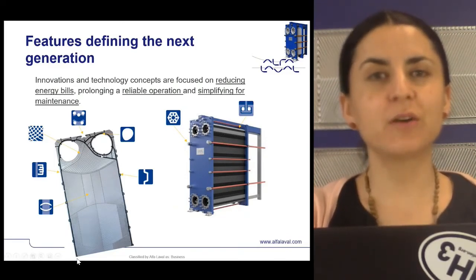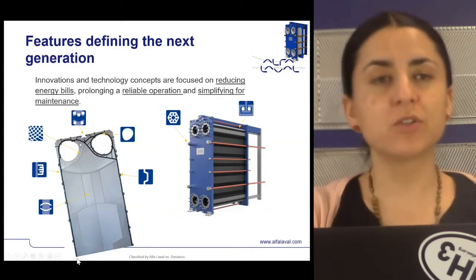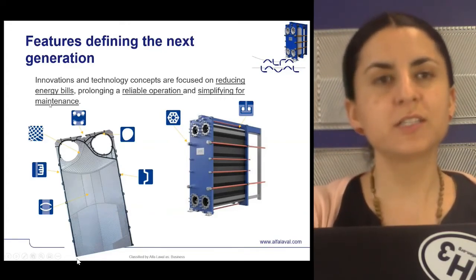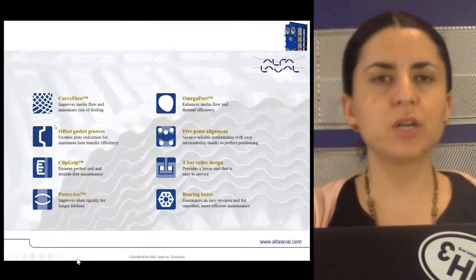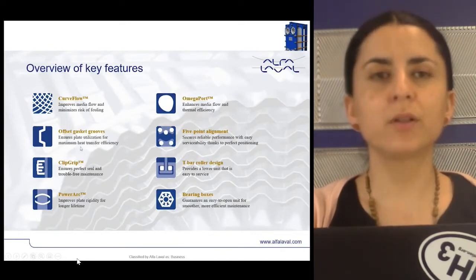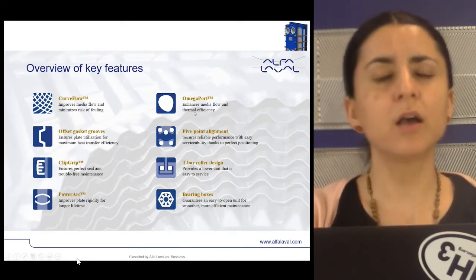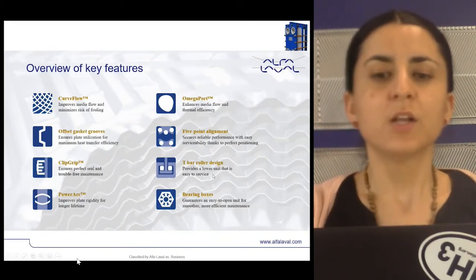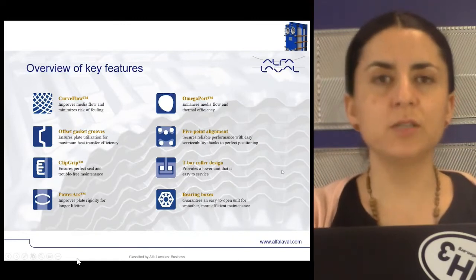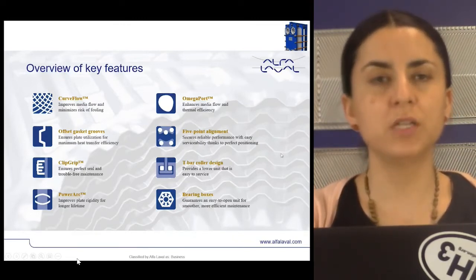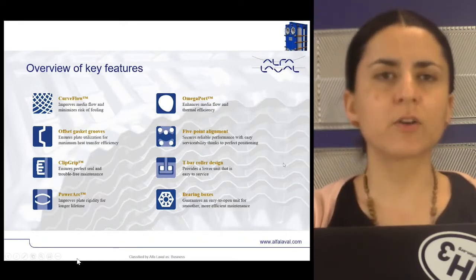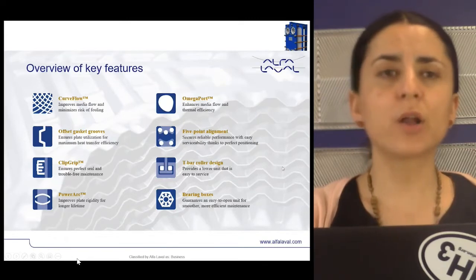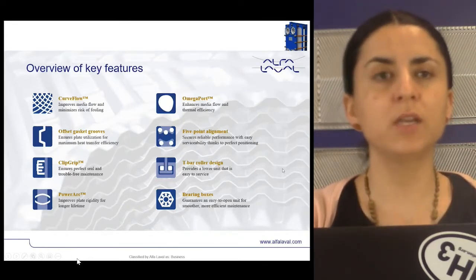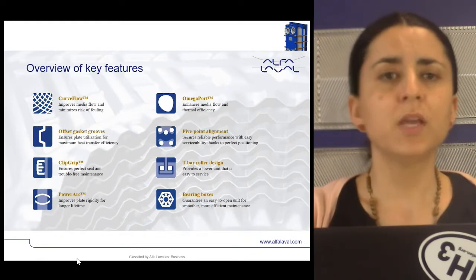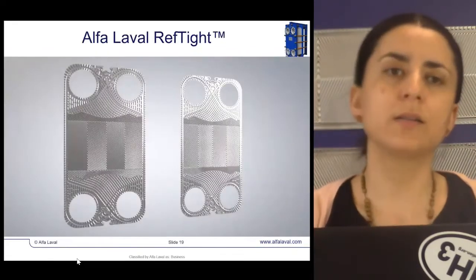Alfa Laval has a new generation of plate and frame heat exchangers that can help you reduce your energy bills, prolong the operation, and simplify maintenance. Some of the new features are CurveFlow, offset gaskets, omega port, 5-point alignment, power arc, clip grip, and T-bar roller. Together, they offer improved thermal efficiency to cut energy costs and help you meet your sustainability goals. They also offer greater mechanical reliability for longer equipment life and reduce the risk of downtime in your operation. Easier serviceability keeps maintenance to a minimum and saves you time, labor, and money on that service.